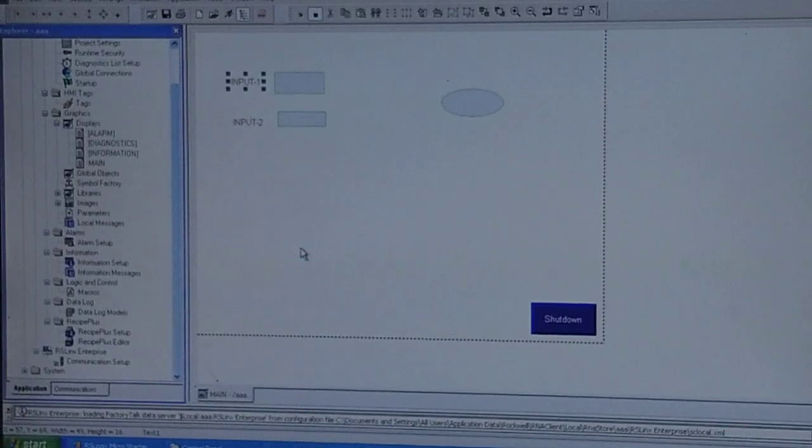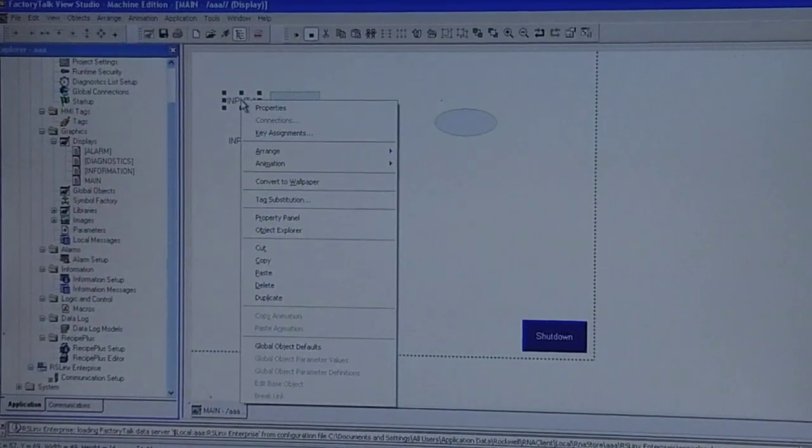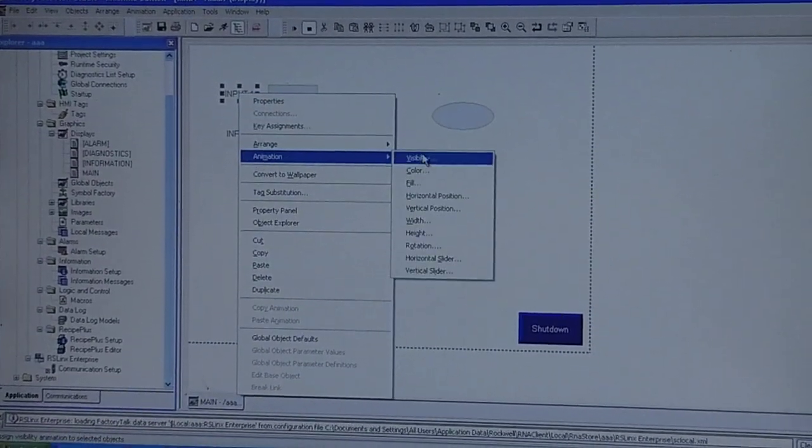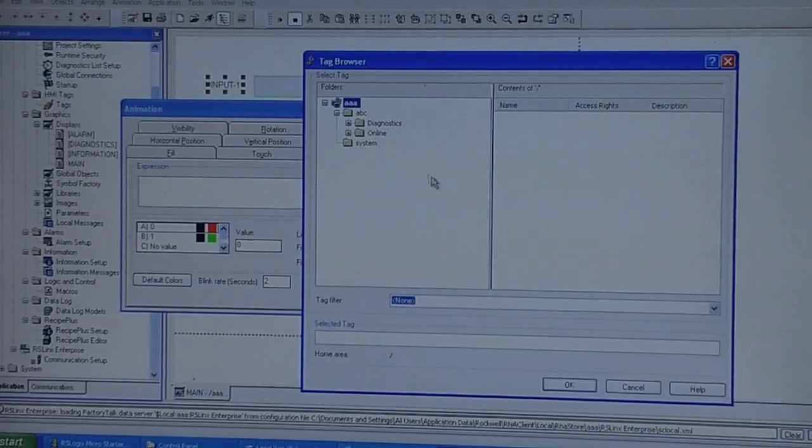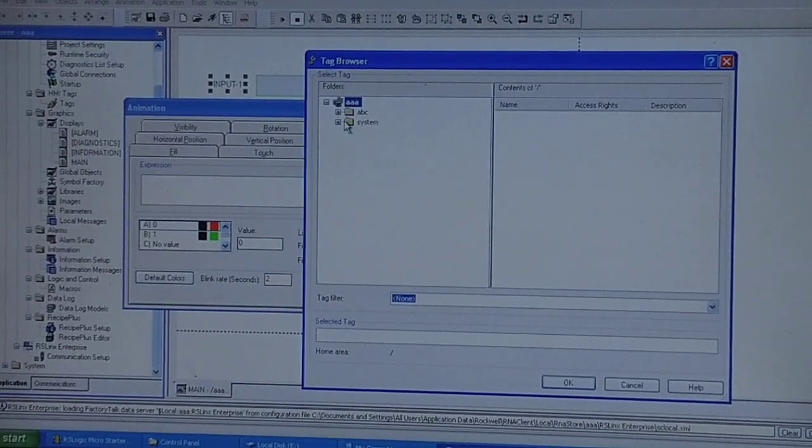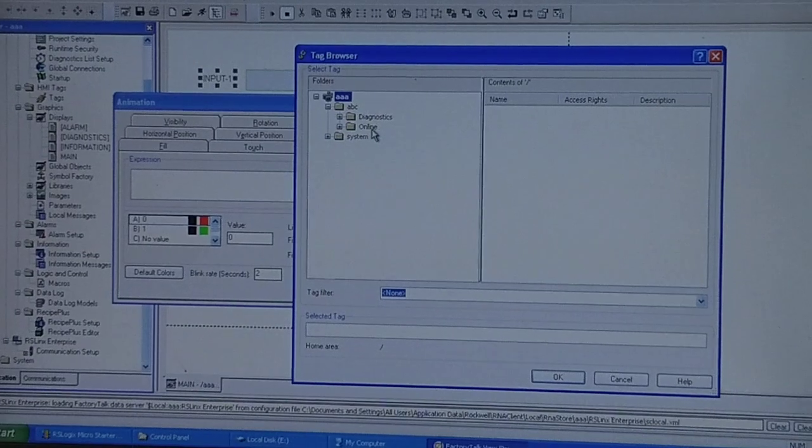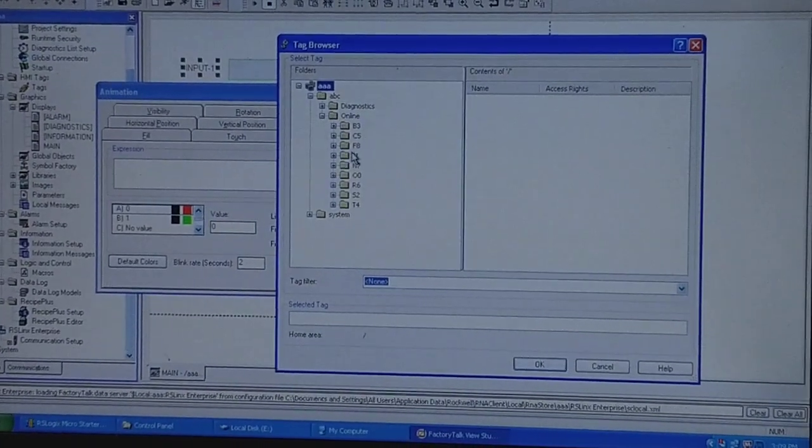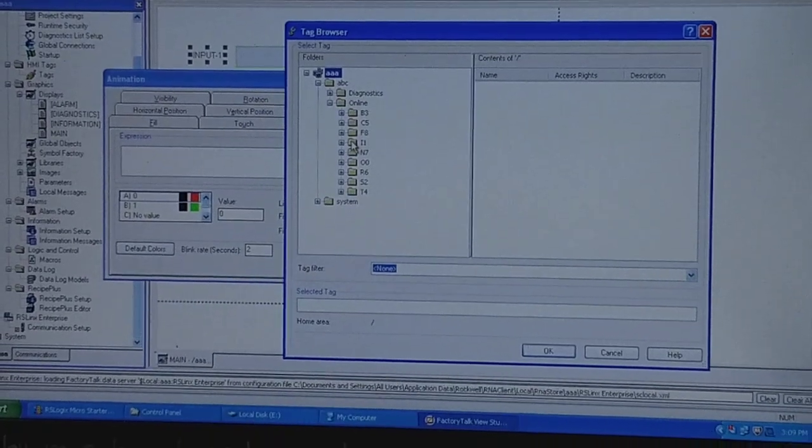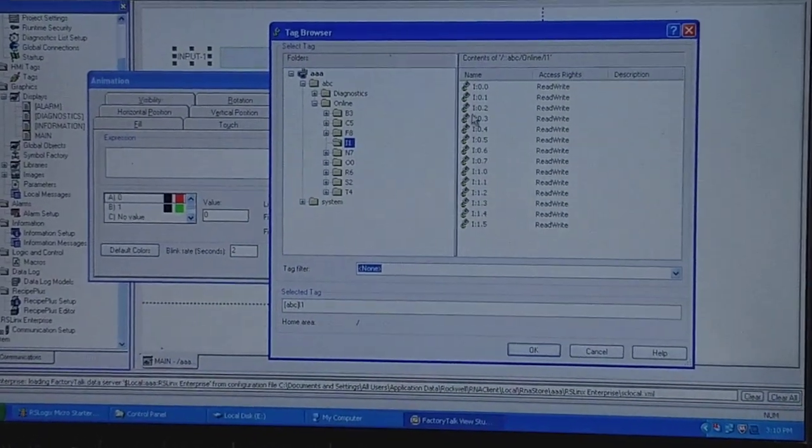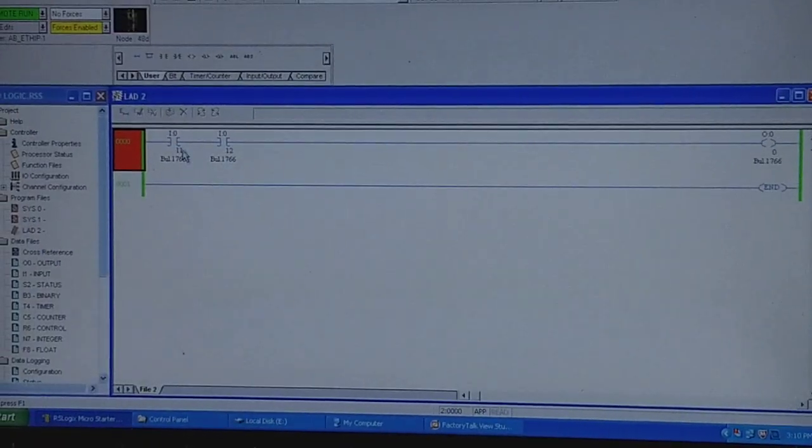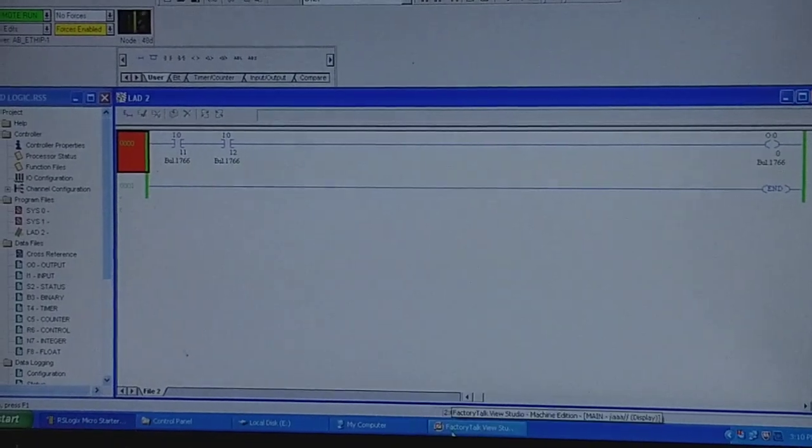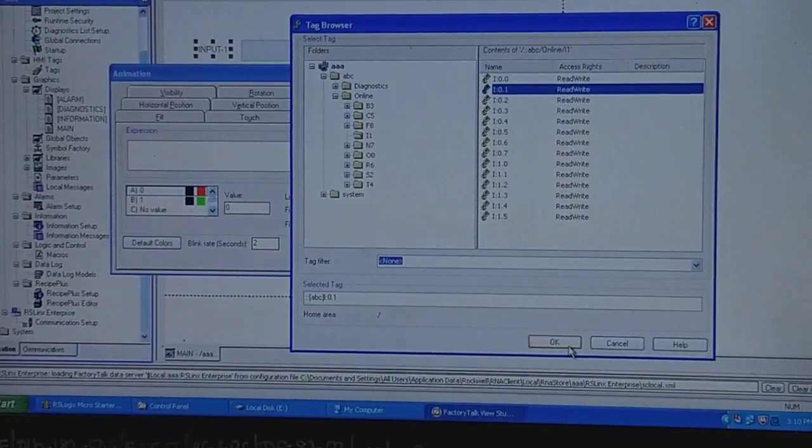We will go for System. We will do tagging for the inputs first. Right-click on the input, then go for Animation, Color. We will go for Tags and here we will refresh all the folders. From that we will select our file name and from that select Online folder. Now as we have to give tagging for the inputs, we will select Input file. As per the notations in the ladder diagram, we have used Input 1 and Input 2, so we will use similar notations here. Input 1, we will do it okay and apply.